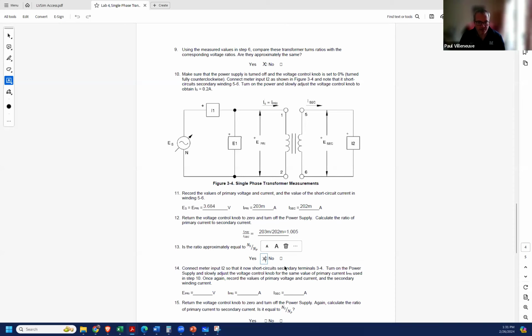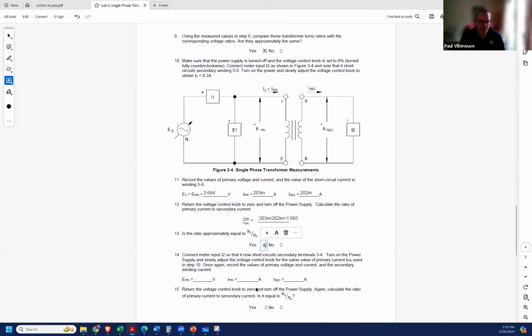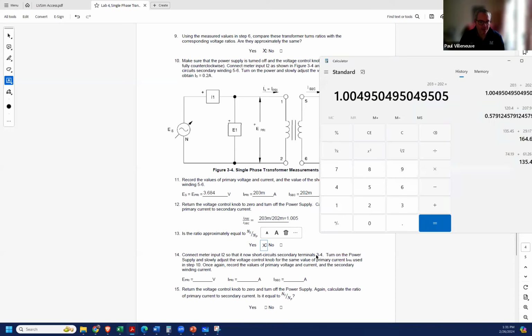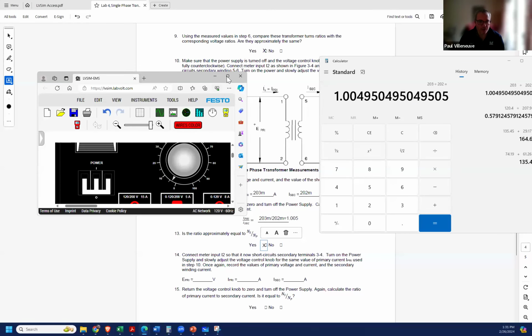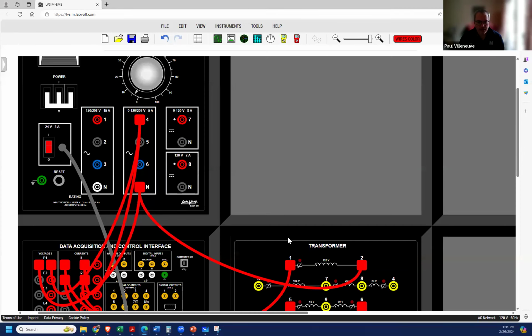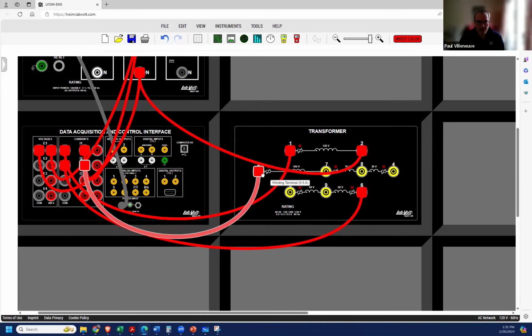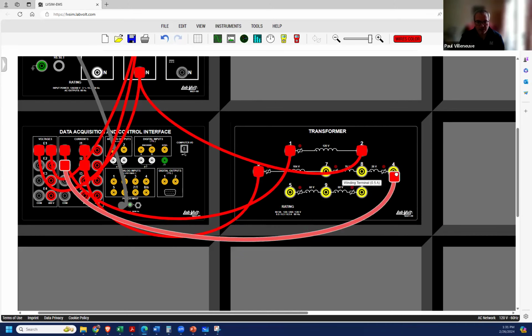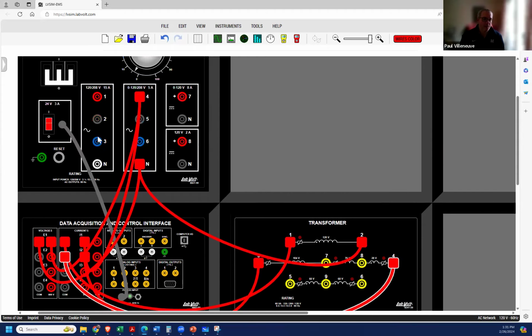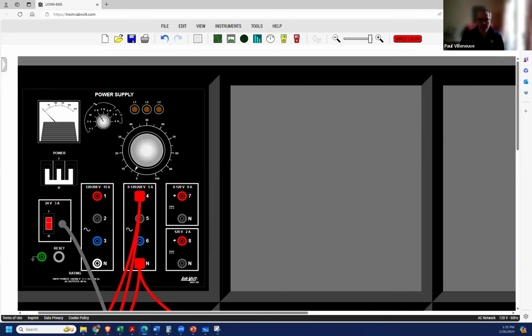So I'm feeling pretty good about this one. Now we're going to modify the circuit. My change is that I'm no longer on terminals 5 and 6, I'm going to be on terminals 3 and 4. So I switch positions over, and I'm de-energized, so terminal here, terminal here. Hopefully I don't need to adjust this, but let's minimize it and get ready to adjust by bringing up the metering window.